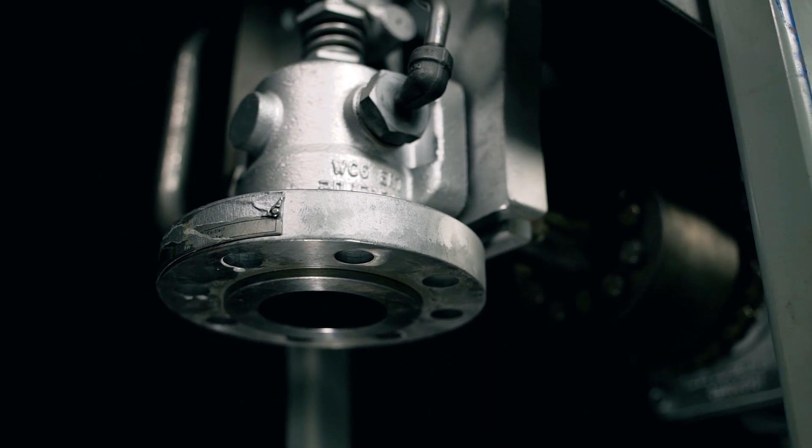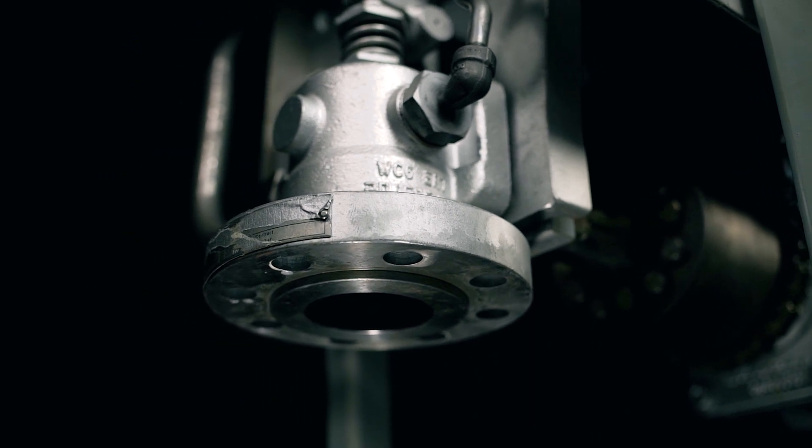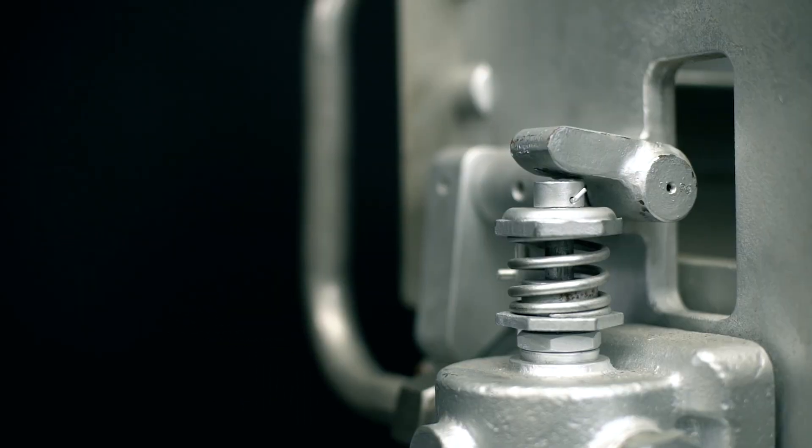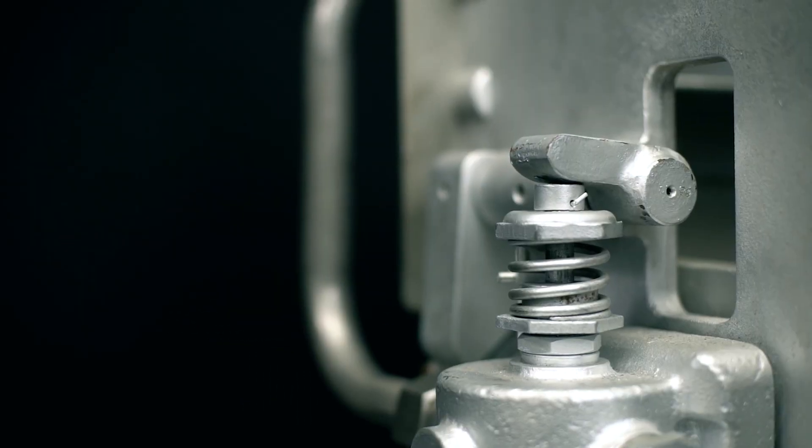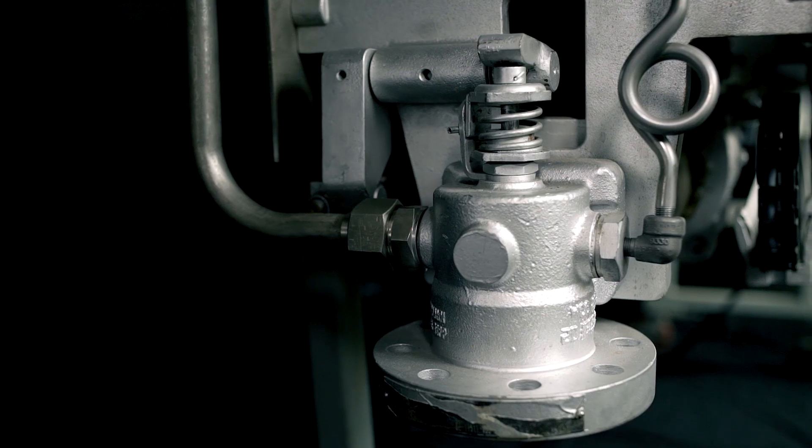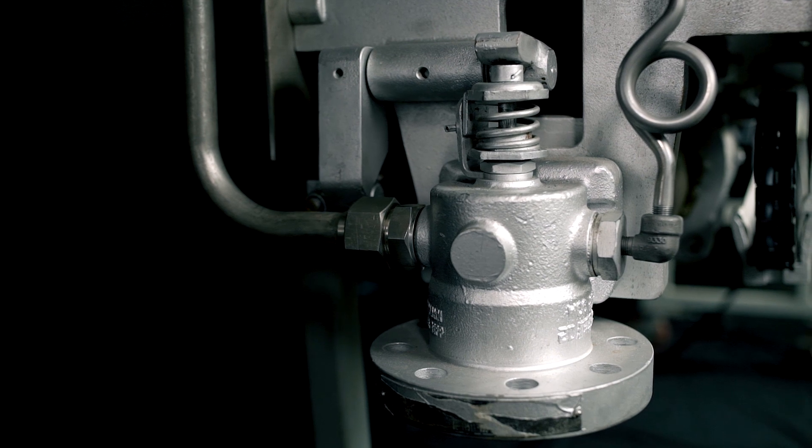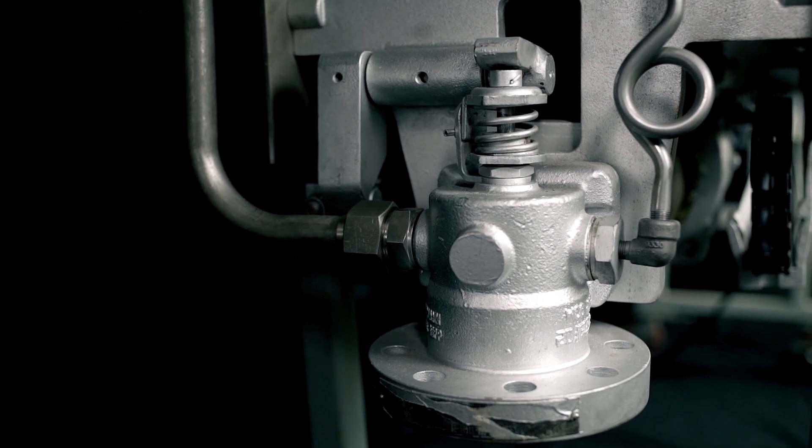Steam leaks could come from the poppet valve gasket, out of the valve stem packing, or it could be coming out of the side ports of the poppet valve.